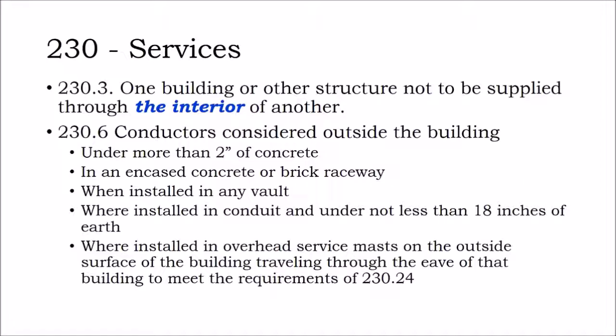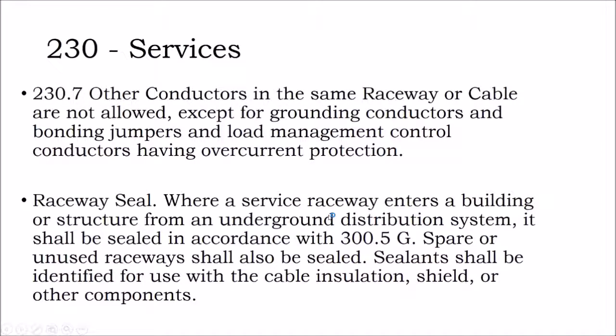Conductors, one building or other structure not supplied through the interior of another. So if I have a row home, I'm not allowed to take the power lines from outside the building and then put them through the floor of another building and then tie those into a third building on the other side. Unless there are special conditions, like I'm burying them in concrete or putting them in a concrete raceway, or there's a vault, that's just a concrete barrier around where the cables are going under. So essentially it's saying the cables need to be protected, and heavily protected, if they're going from unit to unit. Basically, they have to be encased in concrete.